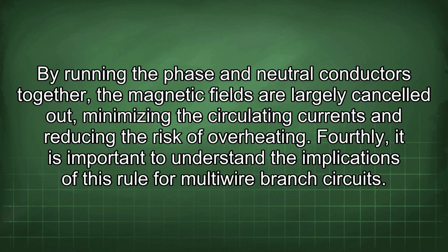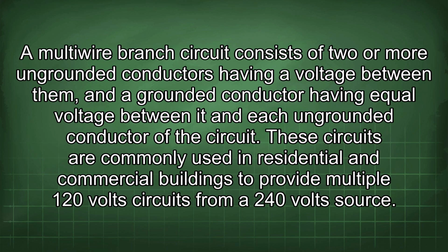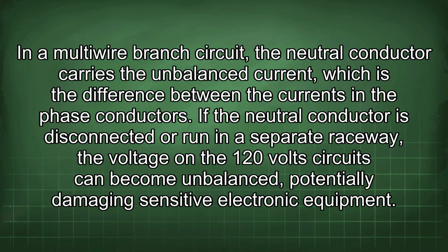Fourthly, it is important to understand the implications of this rule for multi-wire branch circuits. A multi-wire branch circuit consists of two or more ungrounded conductors having a voltage between them, and a grounded conductor having equal voltage between it and each ungrounded conductor of the circuit. These circuits are commonly used in residential and commercial buildings to provide multiple 120-volt circuits from a 240-volt source.